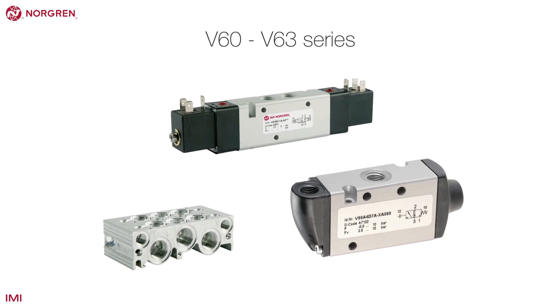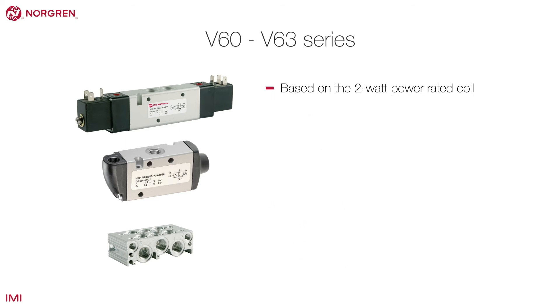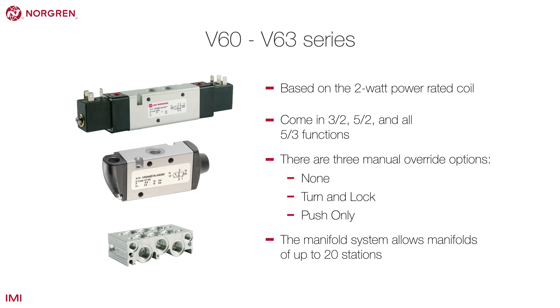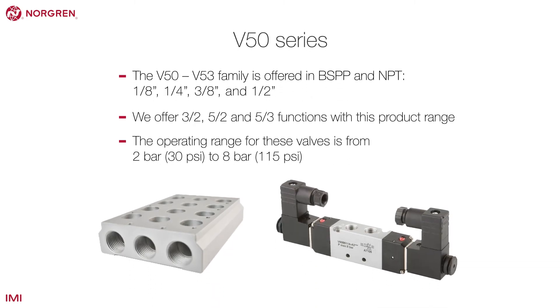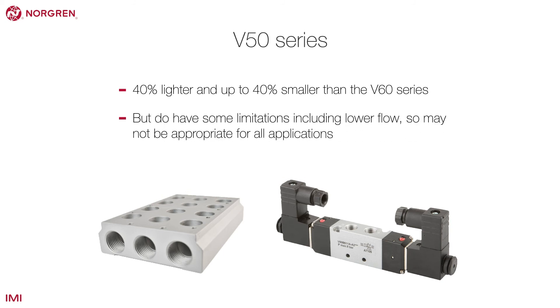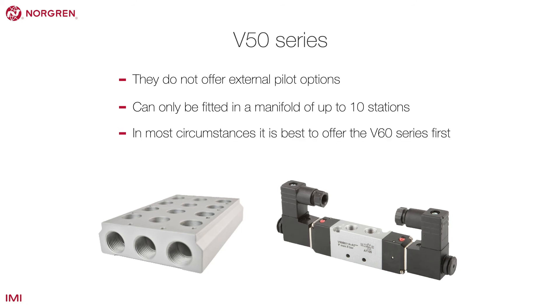The V60 to V63 valves are Norgren's complete family of core inline pilot operated and solenoid pilot valves, based on the 2-watt power rated coil and available in 3-2, 5-2 and all 5-3 functions. There are three manual override options: none, turn and lock, and push only. The manifold system allows manifolds of up to 20 stations with options for using an external solenoid pilot. The V50 series is also a family of inline solenoid and pilot valves offering a low-cost alternative — they are 40% lighter and up to 40% smaller than the V60 series, but have some limitations including lower flow, no external pilot option and can only be fitted in a manifold of up to 10. In most circumstances it is better to offer the V60 series first.